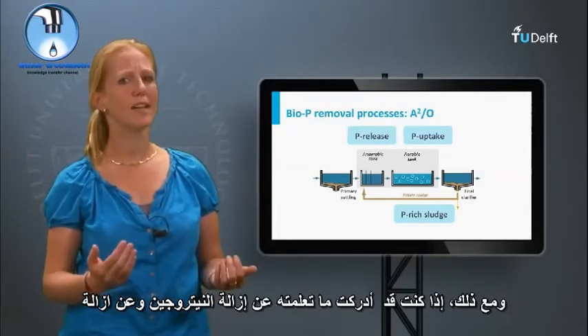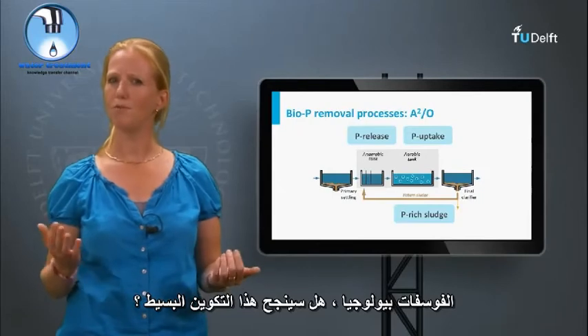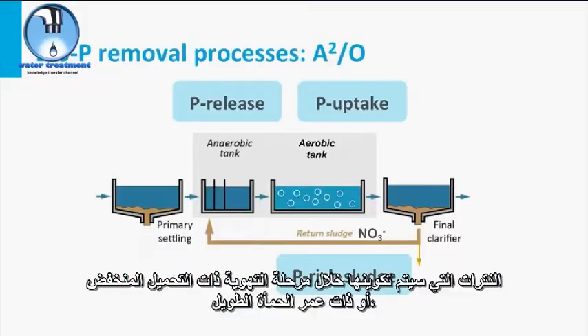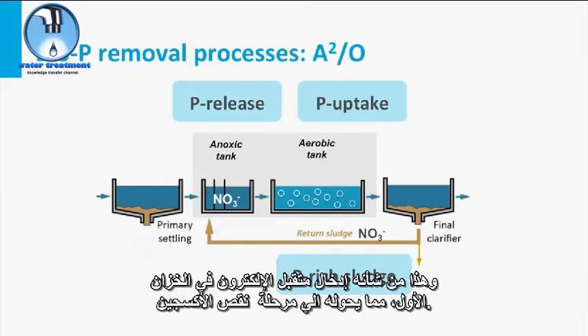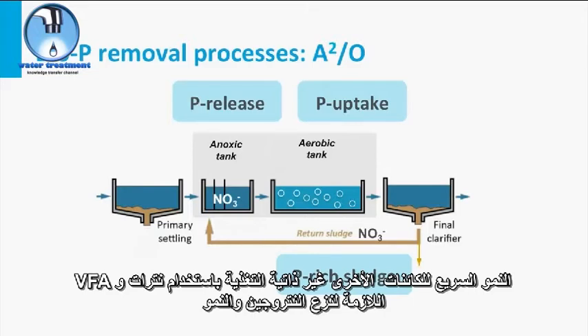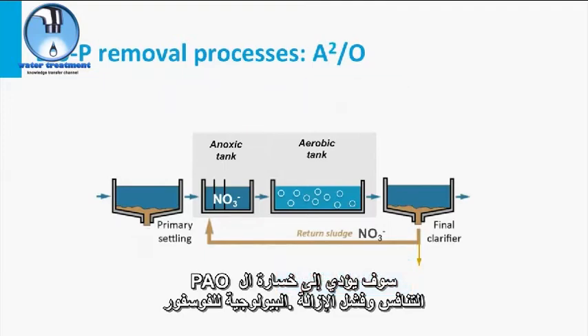However, if you consider what you learned about nitrogen removal alongside biological phosphate removal, would this simple configuration work? The nitrate that will be formed during aeration at low loading or long sludge ages would be returned to the anaerobic tank with the return sludge, making it anoxic. The rapid growth of other heterotrophs using nitrate and the VFA required for denitrification and growth will result in a competitive loss of the PAO and the failure of biological P removal.